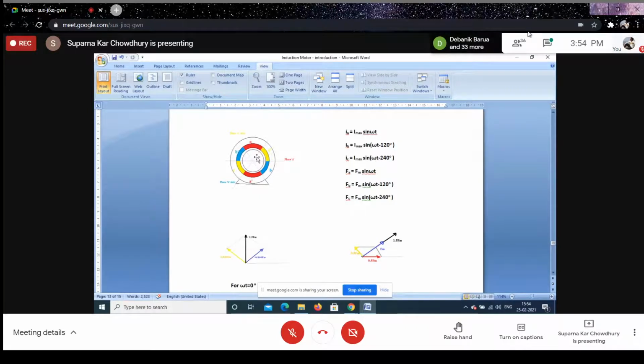So the flux cutting the rotor conductors changes, meaning the rotor conductor flux linkage changes with time, and an EMF is induced in the rotor conductor. Since the rotor is short-circuited on itself, current flows, and as this current interacts with the flux, torque is produced. The current flowing through the rotor winding itself creates another field, and these two fields, being free to rotate, try to lock with each other and ultimately run at a common speed.